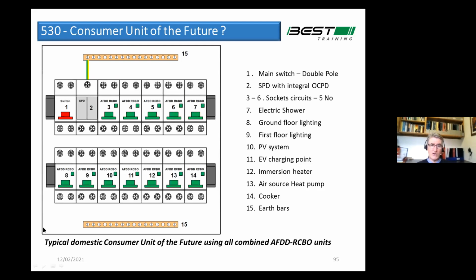It says metal or non-metallic materials complying with a specific standard for the glow wire test for the material. The other standard, of course, for all consumer units is they must comply with EN 61439, which is the switchgear standard. And part 3 of that standard specifically deals with what they call distribution boards for unskilled people, if you like. So in other words, consumer units in houses where the people resetting the breakers, etc., are non-trained electricians. And they have very specific requirements. So that's one of the changes, okay? Regrettably, it didn't end up as metal. If I was there now, I'd be hammering down the table and insisting that we go metal. I think it's the right way to go personally, and deeper, to give us more space in the consumer unit.